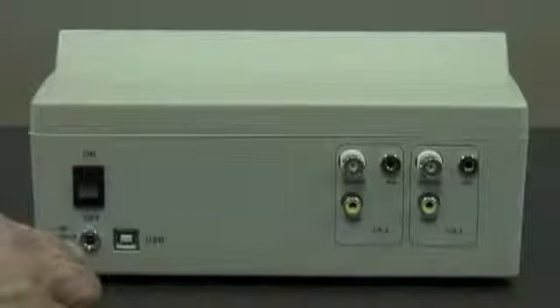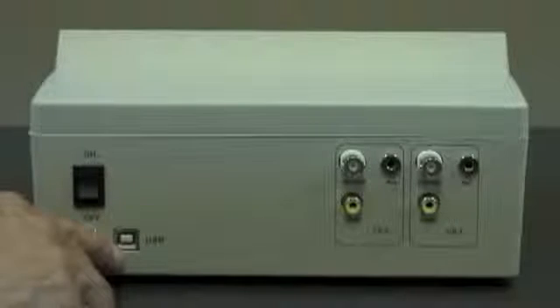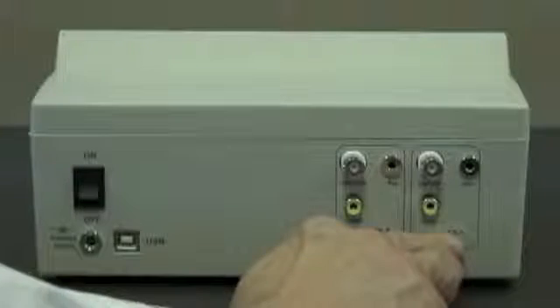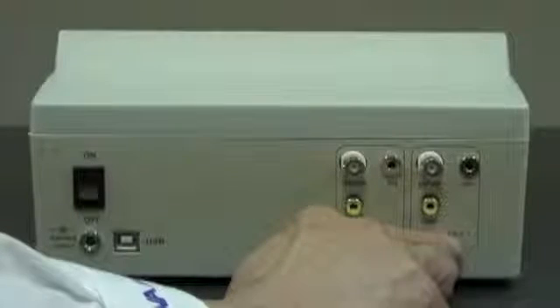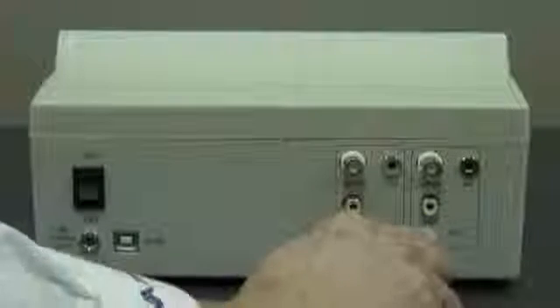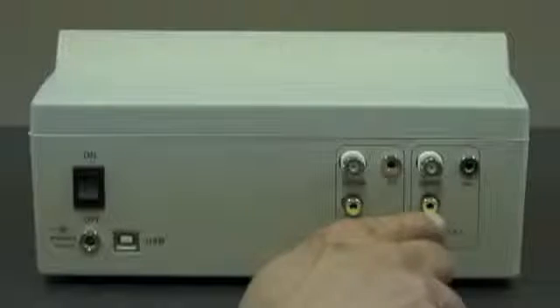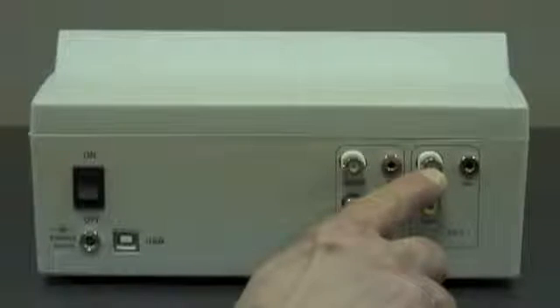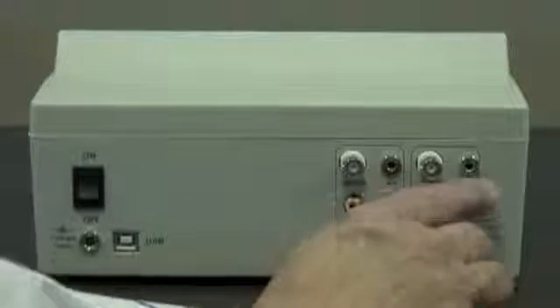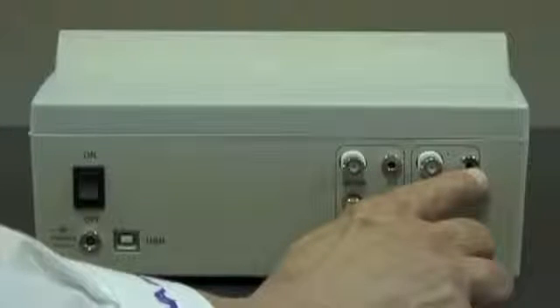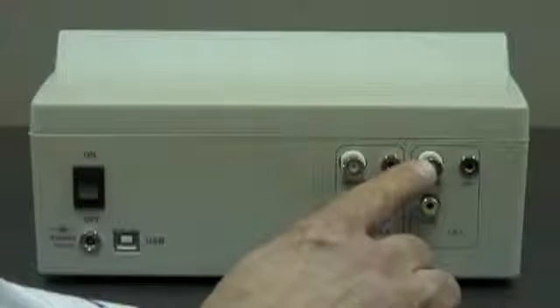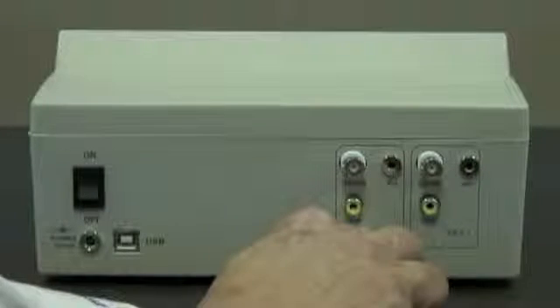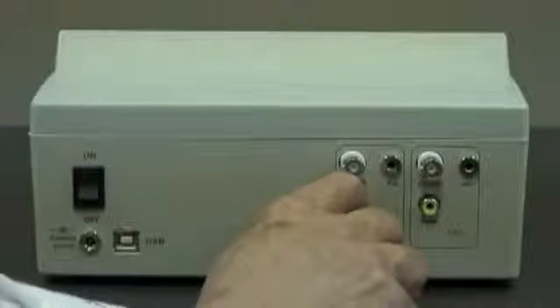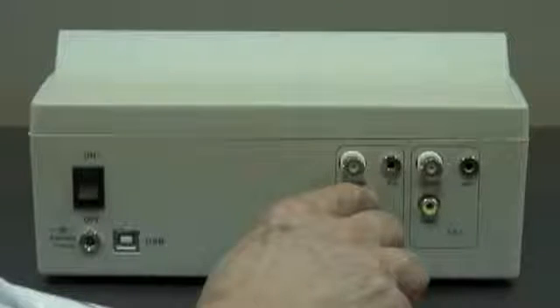When I turn the meter around, I see the on-off switch, the connector for the power cord, the connector for the USB cord which is going to plug into a PC, and then 2 independent channels that are galvanically isolated, which means that when 2 probes are in the same solution, they won't interfere with each other. When I look at channel 1, for example, I see the input for the temperature probe, a BNC connector, which is the input for either a pH or ORP electrode, and in the case that I'm going to use a reference probe as a half cell, I simply plug it into this connector and then plug the indicating probe into this connector. Exactly the same thing for channel 2, with the exception that we're going to be working with an ion selective electrode and or an ORP probe.